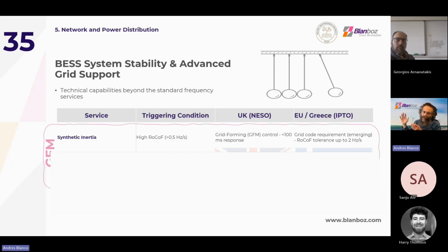We have the other side, and these are more on the stability and advanced grid support. It doesn't only need the grid forming capabilities, but grid following as well. This again is more on the balancing area. We have the synthetic inertia, and the trigger condition is having high variation on the rapid change of frequency, anything above 0.5 hertz per second. In the UK, your system has to be in grid forming control mode, and it needs to be capable of responding in below 100 milliseconds, which is very fast. And again, this is another of the beauties: batteries can perform very well.